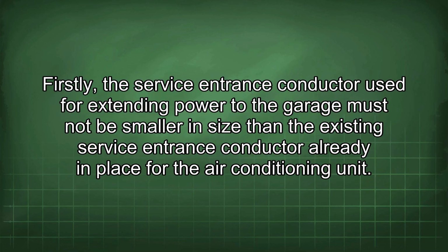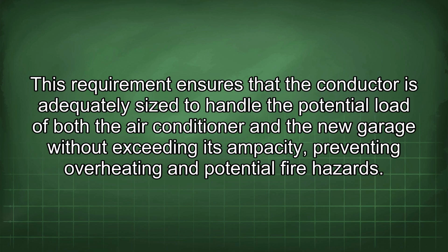Firstly, the service entrance conductor used for extending power to the garage must not be smaller in size than the existing service entrance conductor already in place for the air conditioning unit. This requirement ensures that the conductor is adequately sized to handle the potential load of both the air conditioner and the new garage without exceeding its ampacity, preventing overheating and potential fire hazards.